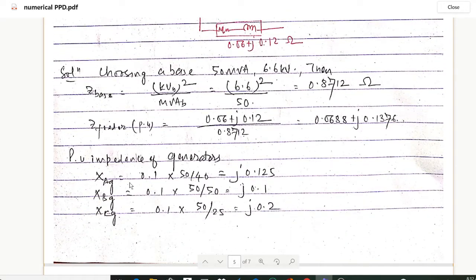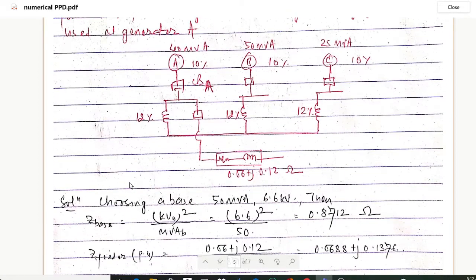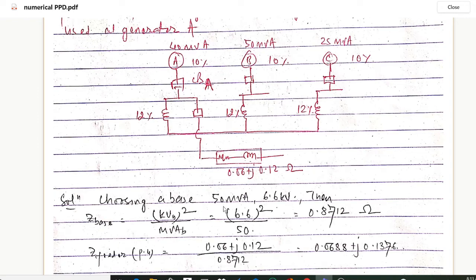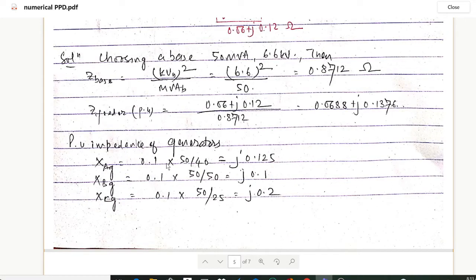For per unit impedance of the generators: the reactance of each generator is given as 10%. The old MVA for generator A is 40 MVA, for B is 50 MVA, and for C is 25 MVA. With new base MVA of 50 MVA, the per unit reactance of generator A is 0.1 × (50/40) = 0.125. For generator B, it is 0.1 × (50/50) = 0.1.